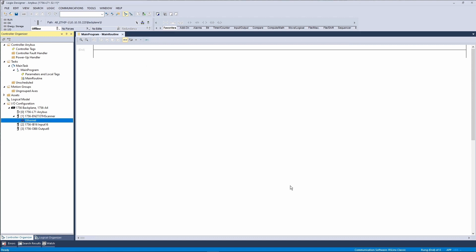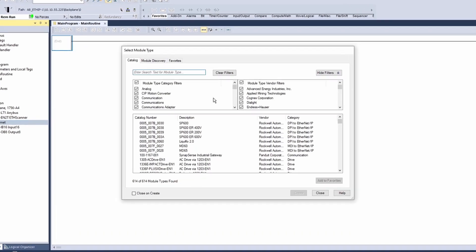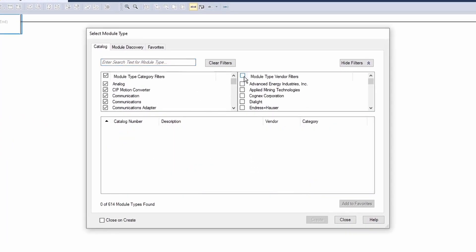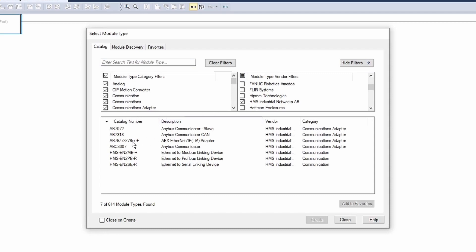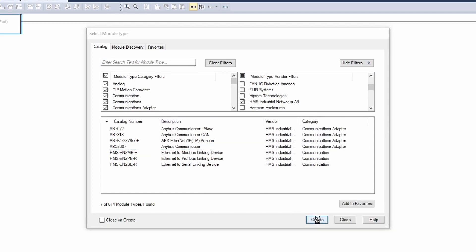Now we can add the module under the PLC scanner. Right-click on the Ethernet connection and select new module. Sort by vendor type in the select module type window and select HMS Industrial Networks. Then select the Anybus Communicator and click create.